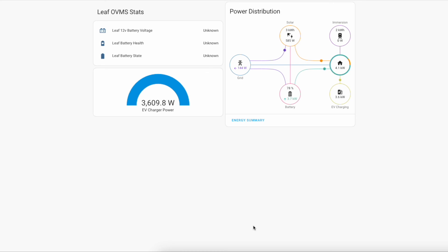Sorry, we'll stop exporting energy from the battery and we'll instead start pulling all our power from the grid including charging the battery. And that should start happening about now. And here we go. So we can now see the power going into the battery and into the EV. From this I think we can conclude the automation's a success.